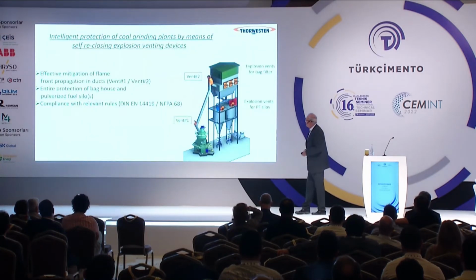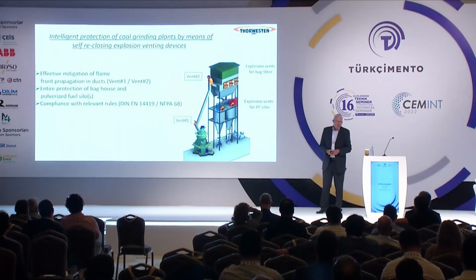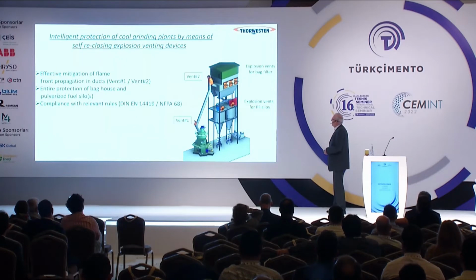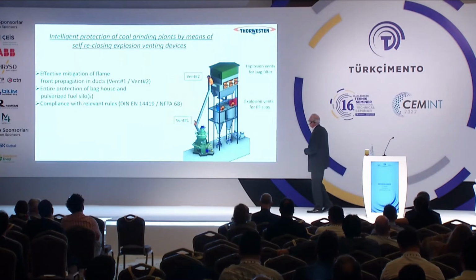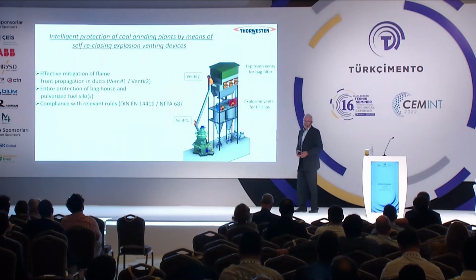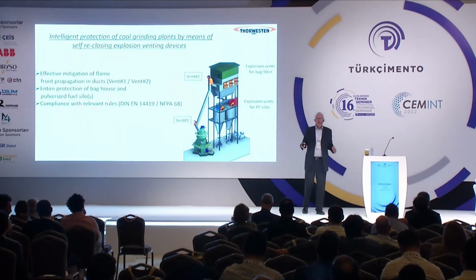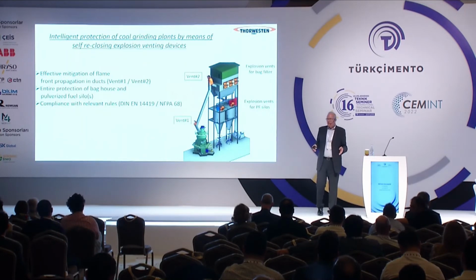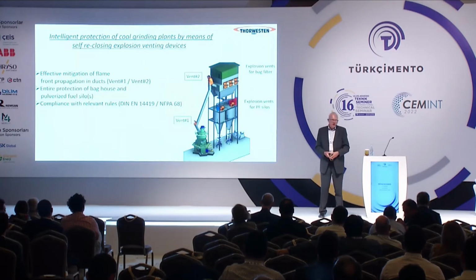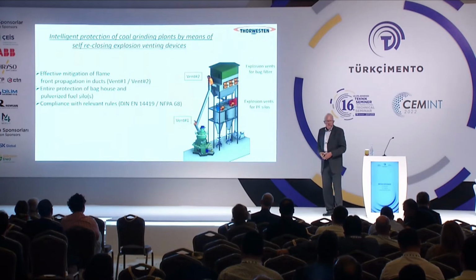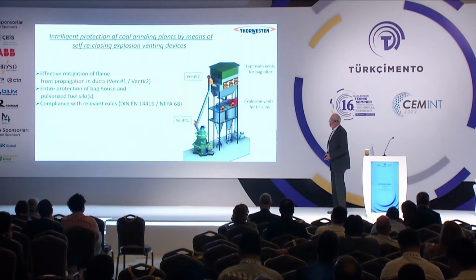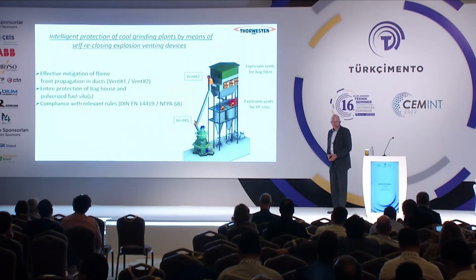What we are doing in terms of coal grinding plants is shown here. This is a typical sketch of a coal grinding plant, which is divided into three sections. The first section I want to explain is the ductwork protection. Here we are talking about a physical phenomenon called flame front propagation in ducts, and that needs to be mitigated accordingly. Therefore, Thorwesten invented a special system some years ago in order to mitigate this flame front propagation effectively.